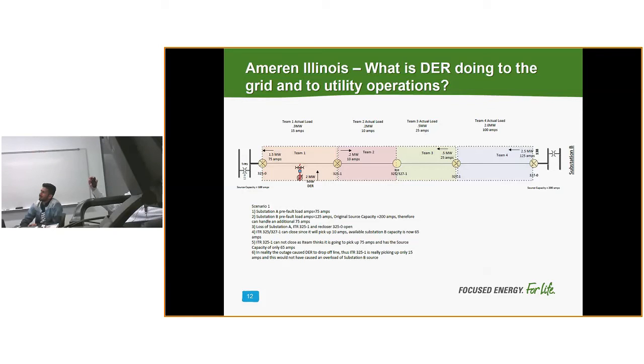And different vendors are providing different solutions. So this scheme here, we use, for example, S&C and interrupters. S&C would give you a device that goes here that would connect to all their interrupters. G&W will give you a different device that could go in here and communicate to their logic. Some would use just SCADA. So a central block that sees all this stuff, runs a basic calculation, right? Runs some estimation, and can tell you how much amperage you could and could not pick up. So there are ways to solve it, but these are, again, some of the basic reliability problems that DERs are presenting to our systems.